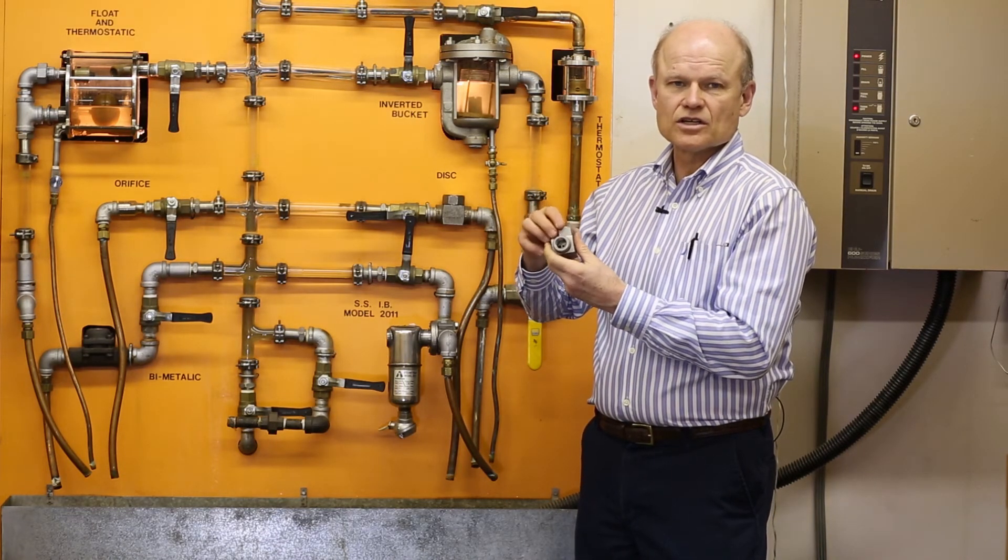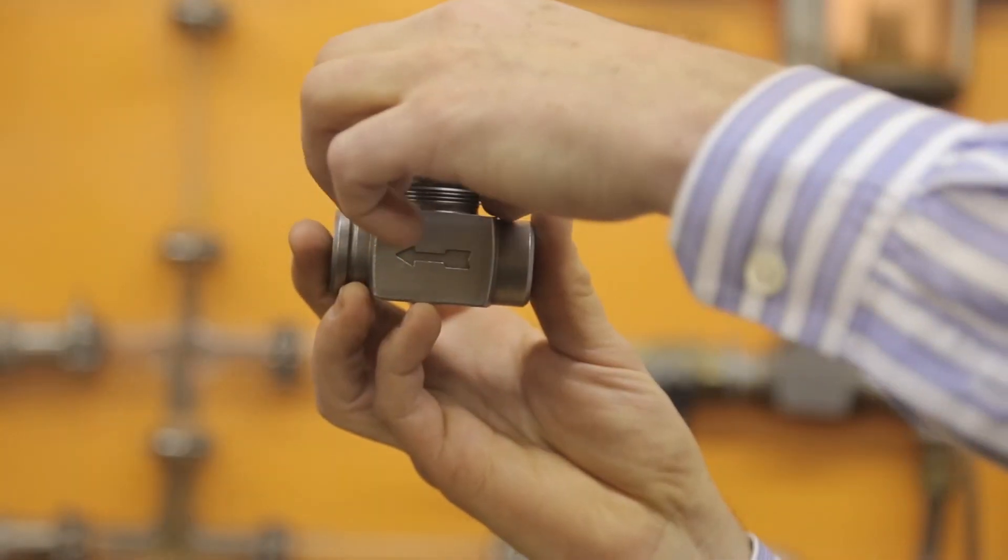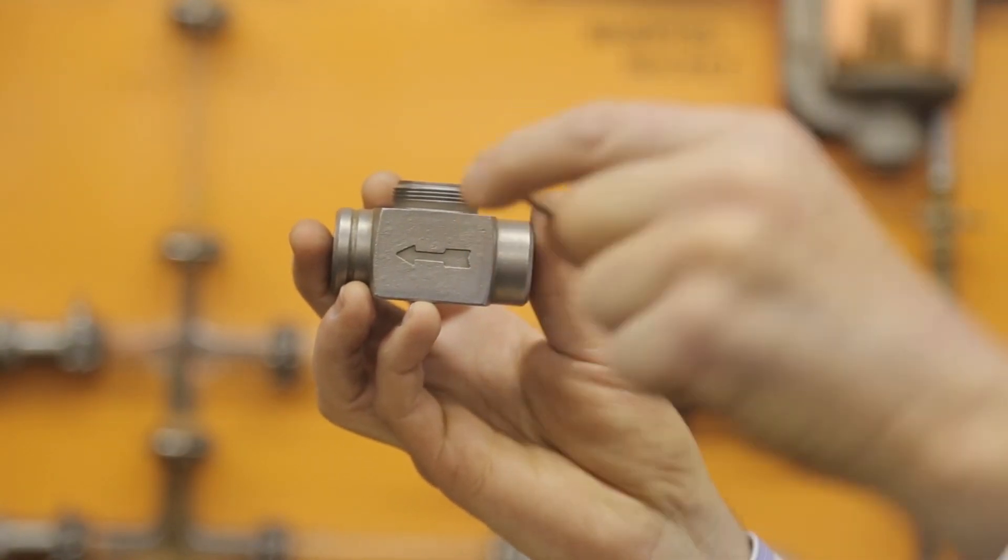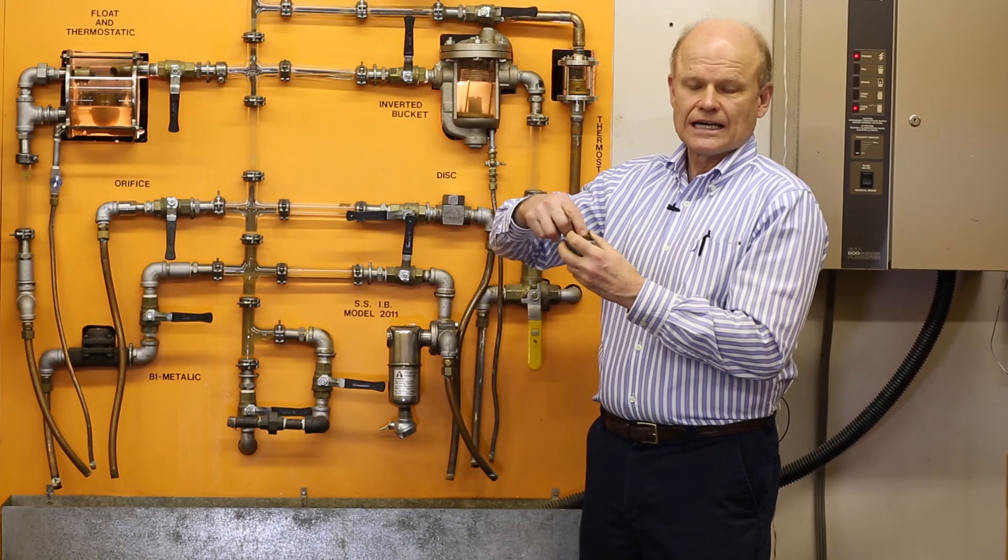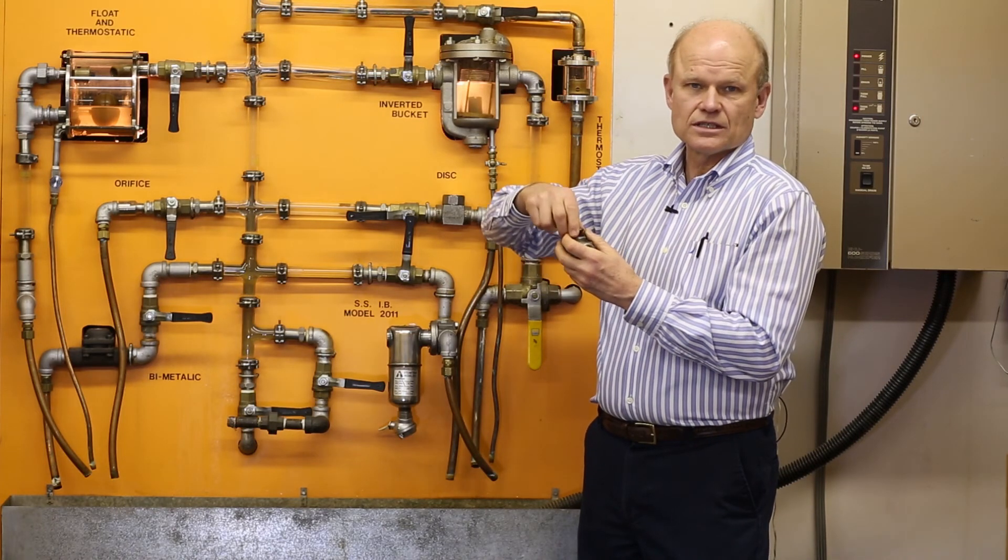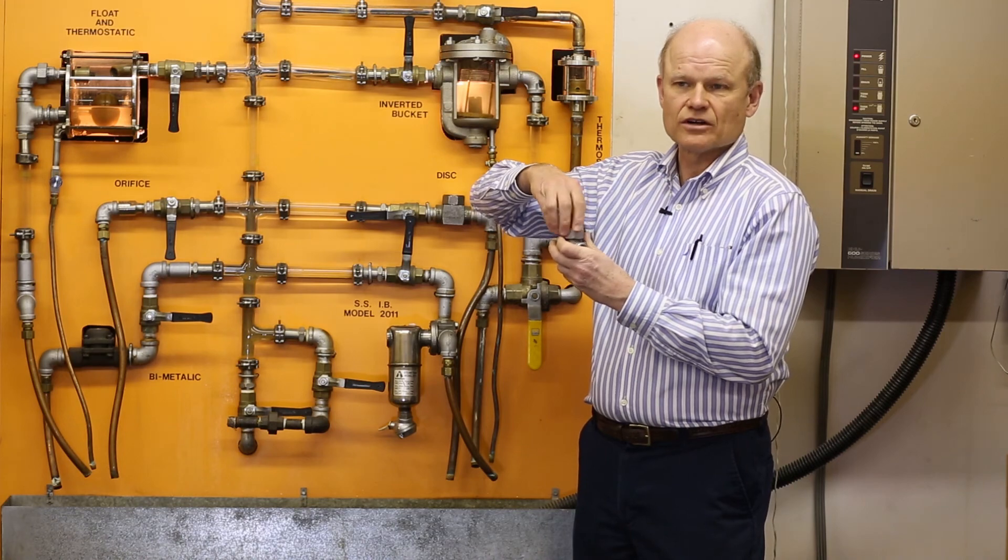So it's not very good on modulation, and is used in areas where it's very durable. There is no issues with water hammer, but the trap does wear out. The disc will wear out, and it does have the shortest service life of all of the generic steam traps.